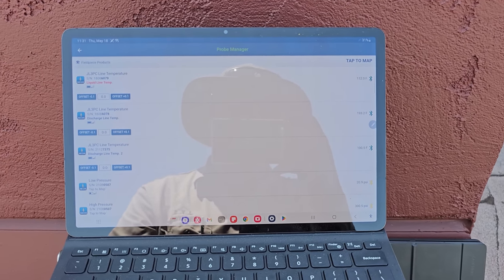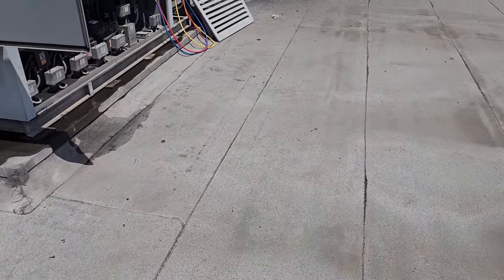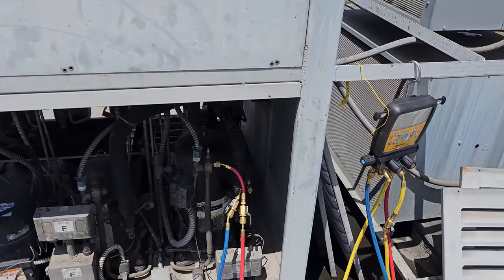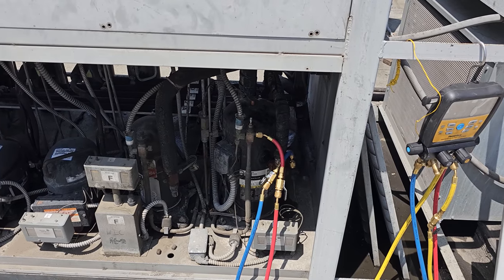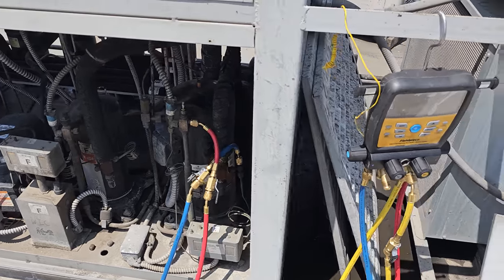It's got contamination probably because of the dirty condenser constantly running with high head pressure. The oil in the system's probably junked, and it's just slowly bypassing. So a mixture of the dirty condenser for a really long time makes the system overheat, and then you get kind of carbon buildup in the system, and usually it gets stuck in the head pressure control valve.